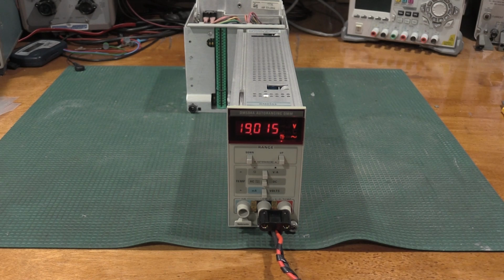And that's within specification of the meter, so everything looks good there. We'll give it a little more. Actually, we'll give it a little less. 1.9 volts. Yep, that's going to be fine. And 190 millivolts. So, looking really, really good on the AC ranges. We'll turn off the AC source and kick it over to DC, and we will turn some voltage on. And I've got negative 10 volts, because I hooked up the leads backwards, so that's reading very well. Negative and positive actually read the same way. Just flip the leads around. There we go. Positive.